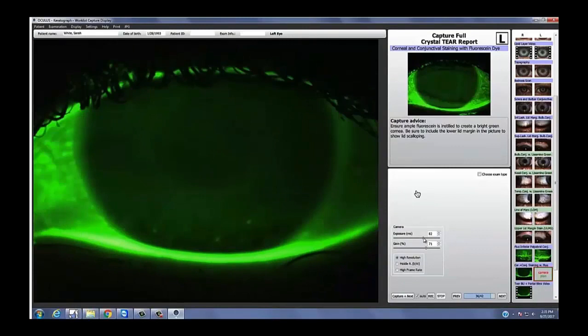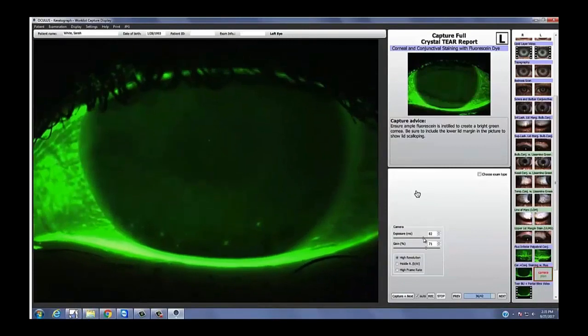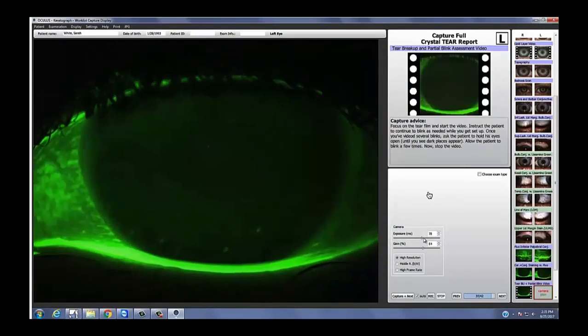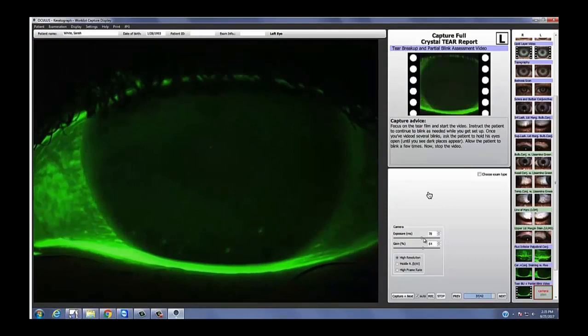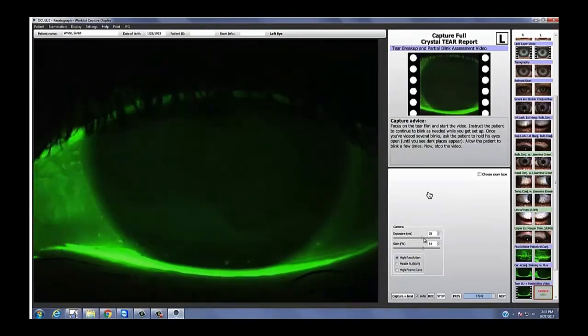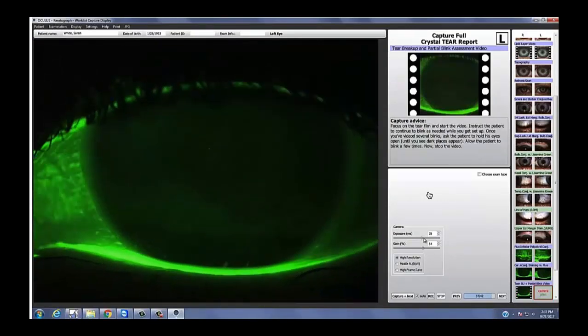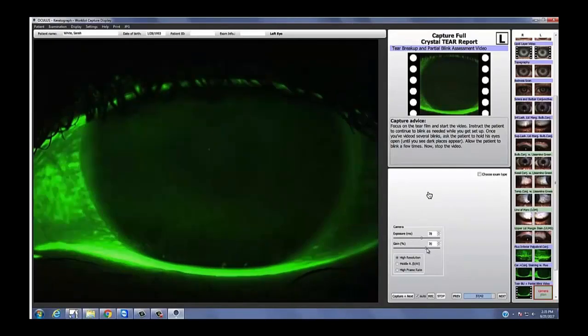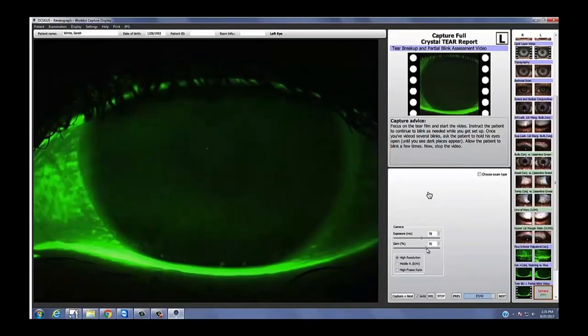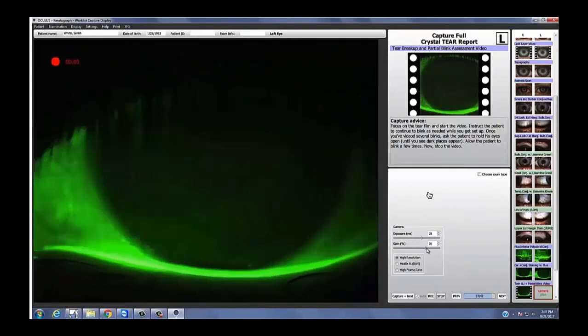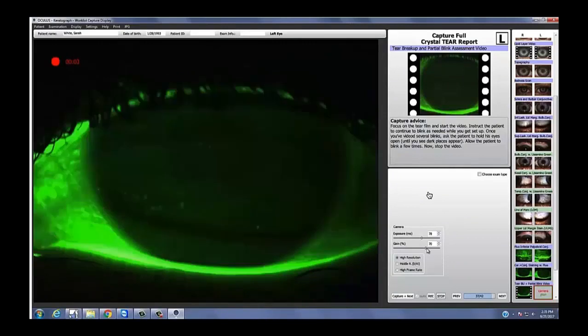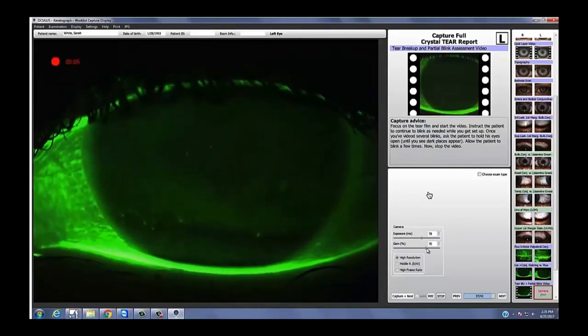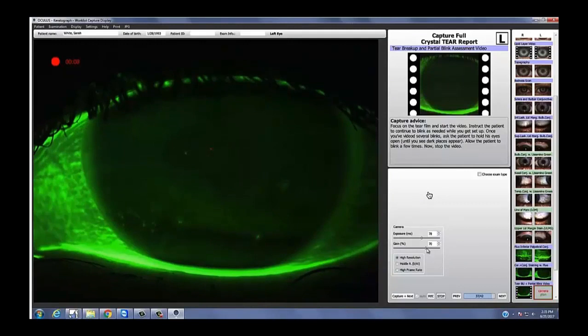By the time I got to the left eye there was a little bit less fluorescein, so I came down here and increased my gain and exposure to see my details better. All of this is adjustable, though we've set it at what will work for most patients. Here's our straight-on image, then we go into our video — have her blink a few times, stay open, see that breakup happening, let her blink again. At this point our capture session is done and it's taken about 10 minutes on average.